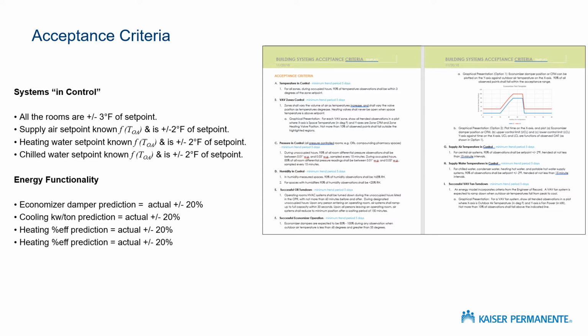Based on the capacity of the cooling system, we'll have an expectation of a certain input power, or kW per ton. So that gives us an expected kilowatt, and we should go out there and measure the kilowatt on the chiller and it should match. It shouldn't be double, right? It should be plus or minus 10 or 20% of our expectation. The same with the heating system. And we should actually know what the CFM is on the air handler, or at least we should know what the anticipated fan power should be in any given hour of the year, and we should be able to look at it, and it should be within reason, or it should not be out of whack, right?